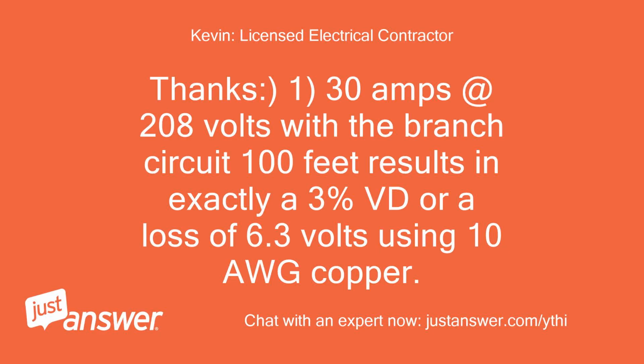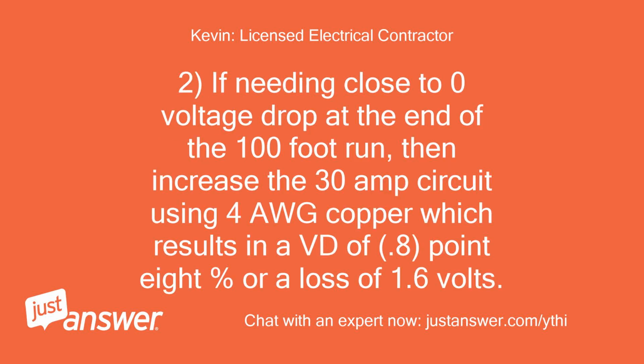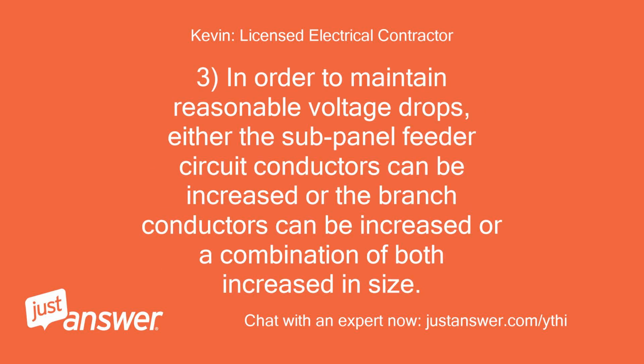1. 30 amps at 208 volts with the branch circuit 100 feet results in exactly a 3% VD, or a loss of 6.3 volts using 10 AWG copper. 2. If needing close to zero voltage drop at the end of the 100-foot run, then increase the 30 amp circuit using 4 AWG copper, which results in a VD of 0.8% or a loss of 1.6 volts. 3. In order to maintain reasonable voltage drops, either the subpanel feeder circuit conductors can be increased or the branch conductors can be increased, or a combination of both increased in size.